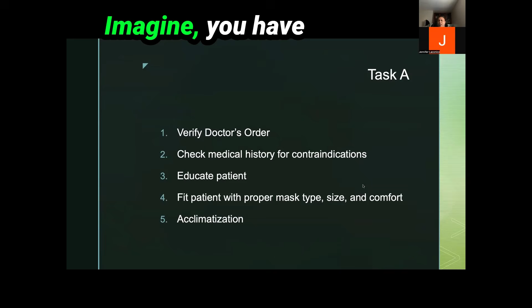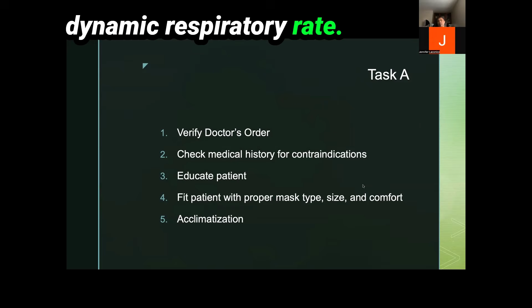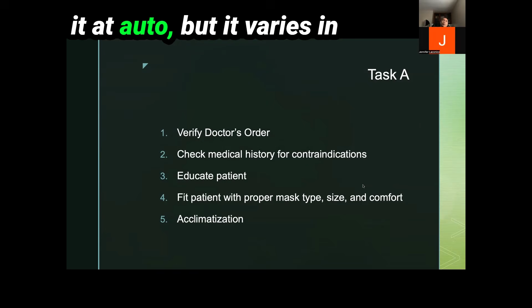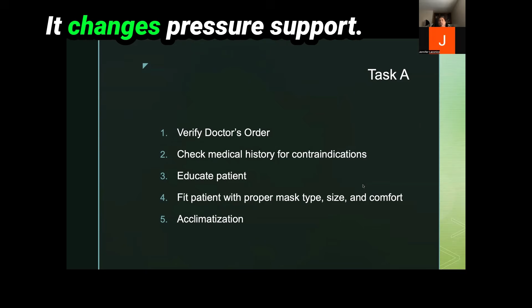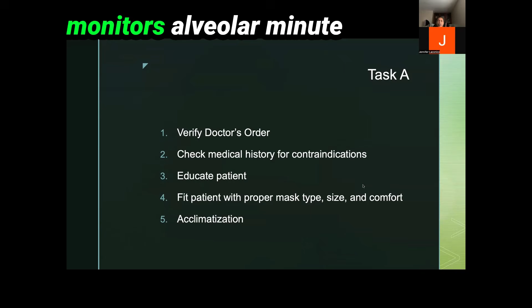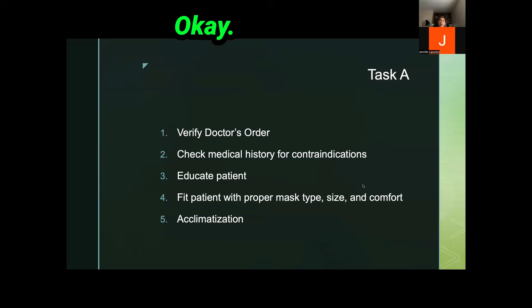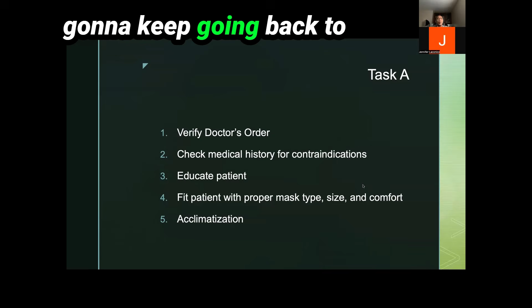Imagine you have another device, ST mode. The rate doesn't change. It's the same. It serves its purpose, right? Constant pressure support, constant IPAP, EPAP, and constant respiratory rate. The ASV has a dynamic respiratory rate. So with Philips, you have to set the rate, or you can put it at auto. But it varies in pressure support. It changes pressure support. It can go from minimum to maximum. So with VAPS, not only can the pressure support change, you also have a device that monitors alveolar minute ventilation or tidal volume. Okay? This is not an easy topic. That's why we're going to keep going back to this until we hash it out.